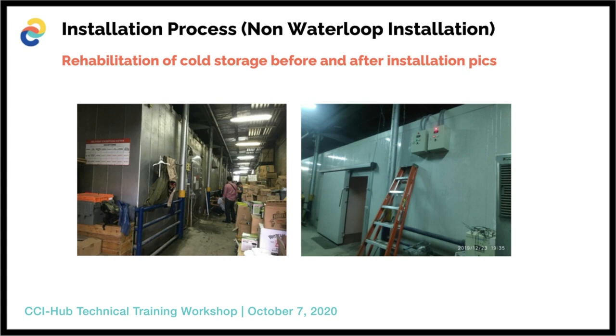The main reason why we use a conventional Freon system for this is that several years prior to us being involved in the renovation, some of the back-end equipment, compressors, compressor racks, were already changed out by Royal Duty Free. So they're relatively new. So in an effort to save money, they didn't want to completely renovate and change these systems that were still fine and operating normally. So they asked that we change the panels that needed to be replaced, but use the conventional R404 rack system on the cold rooms that needed to be changed, and the ones that did not need to be changed they asked us to just renovate and do some PM work and get those systems moving.